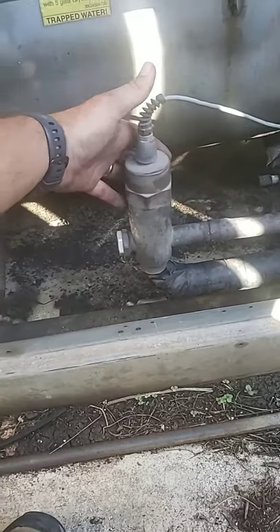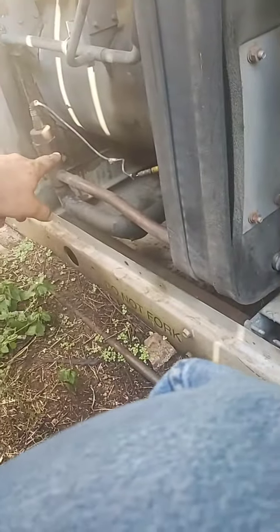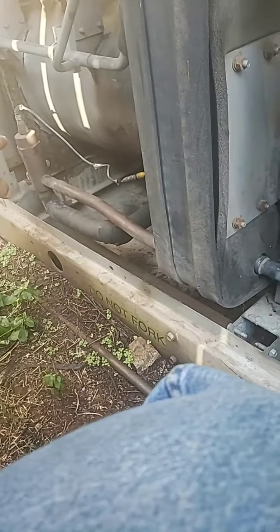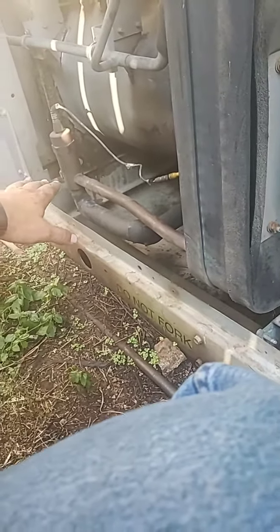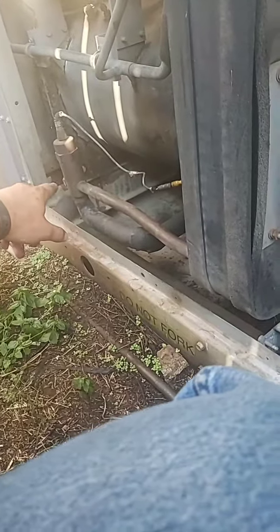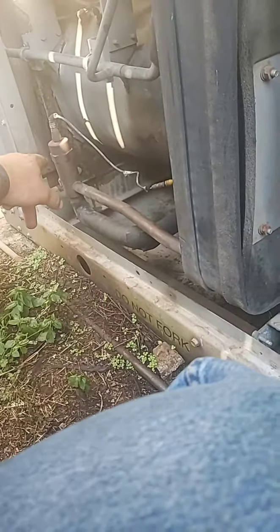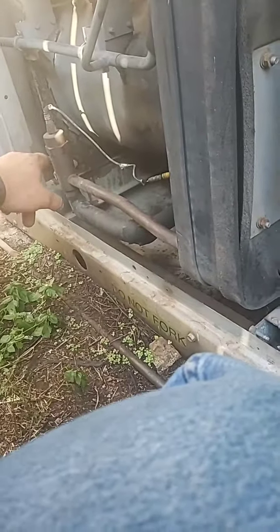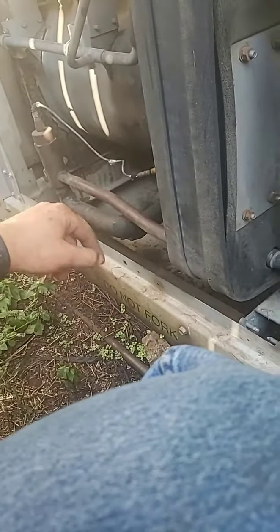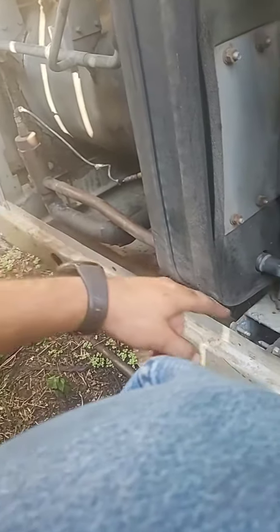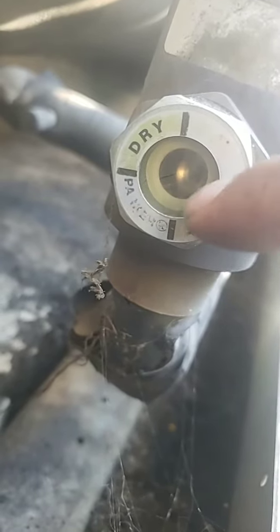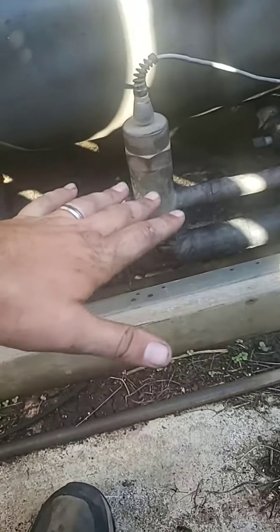The issue it was having with this one was it was pumping itself down, and what I found was that during that calibration cycle on startup, that valve was not ticking. Now it was buzzing. You could hear it and you could feel just kind of a hum, but it was not actually ticking like it was supposed to. And if you look, let's see if we can get a shot of it. You can actually look into the sight glass and you can see the shaft. You kind of see it. I hope it's coming through clearly, but you can see the shaft inside there, and you should be able to see that EXV raising and lowering.